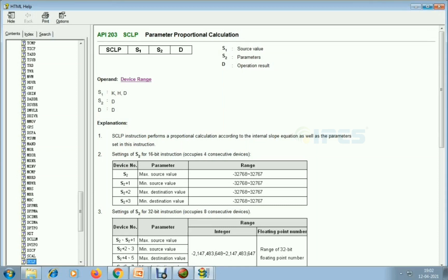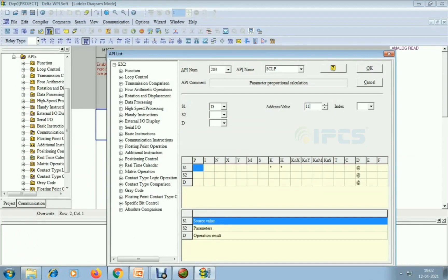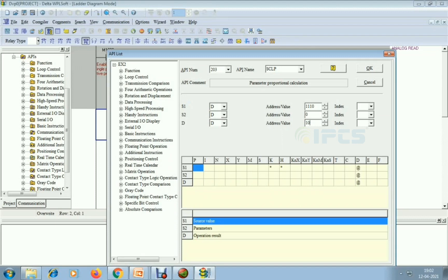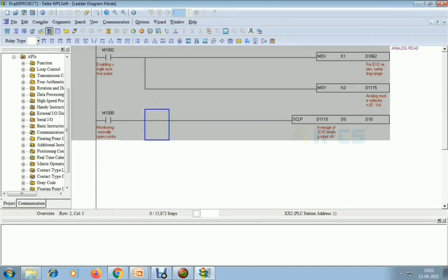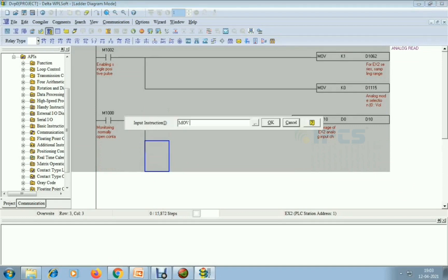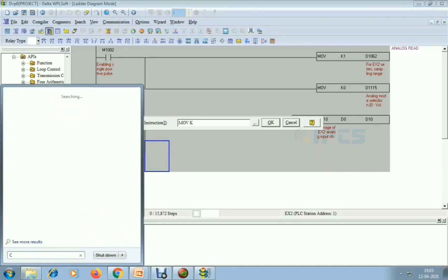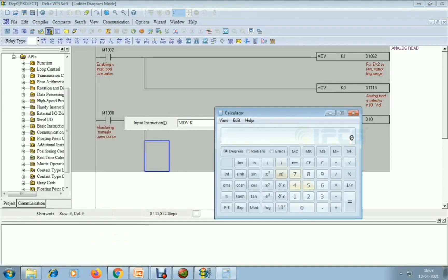I am giving the source value as D1110. Then I'm taking the destination value as D10. I am using M1000, which is always on. After that I am giving the maximum input and minimum input values and the scaling parameters. I'm using MOV commands — this analog input is 12-bit resolution.